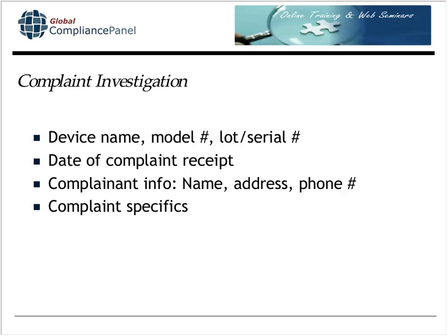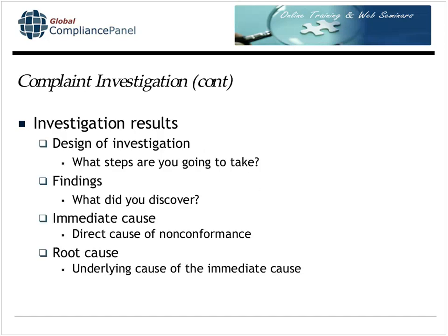Although I do recommend, even if you have a complaint number, that you include the complaint specifics on your investigation record, because that's where you begin to perform your investigation. You don't need to know the device name or date of complaint receipt or specifics on the complainant, but you do need to know the complaint specific, what it was that the customer alleged. Then you're going to perform the investigation and document the investigation results. You're going to begin with a DOI, a design of investigation, which states what steps you are going to take, followed by the findings, which is what you found out, what you discovered.